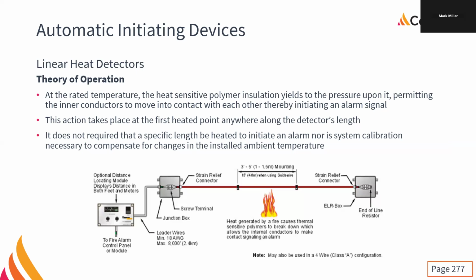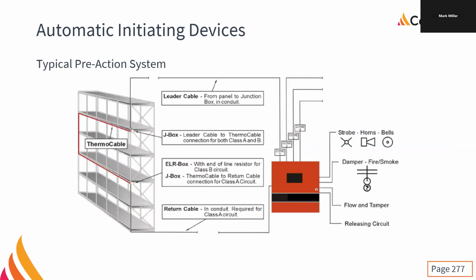And it can also be done as a Class A configuration, right? We can bring the whole thing back as a loop and tie it back into the linear heat detector module and go from there, right? Depending on what they want to do. I haven't done that type of installation yet. I've only ever done it as a Class B. But this is the kind of thing that we can do.